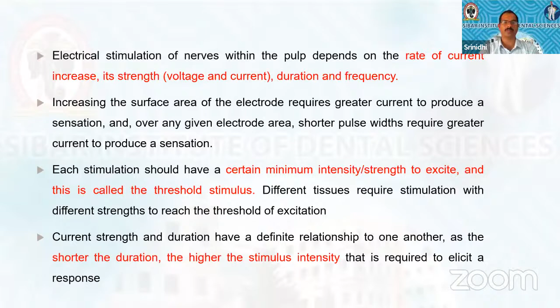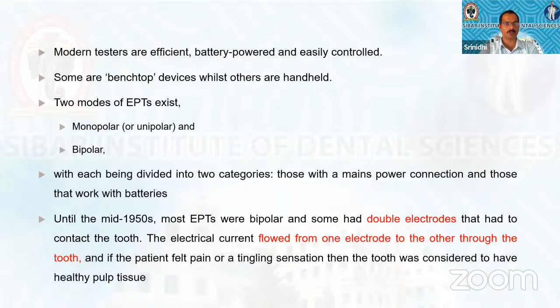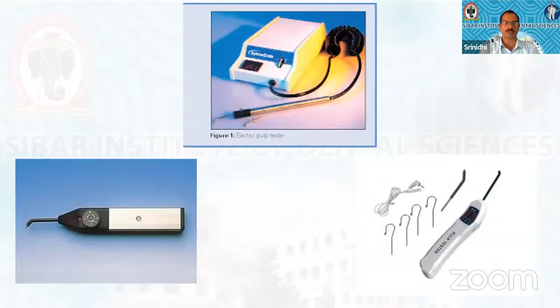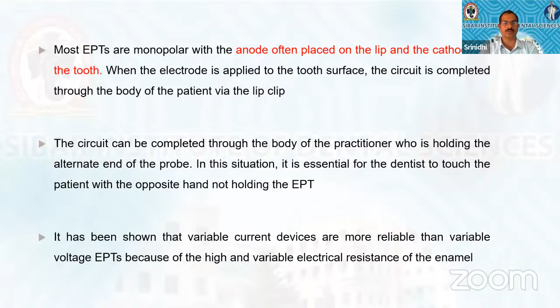So we have two types of EPT, monopolar and bipolar. What we commonly use is the monopolar, where we have a single electrode. In bipolar, we have two electrodes which are placed on the tooth, and the current passes from one electrode to the other. We also have benchtop or handheld devices, and most EPTs are monopolar, with the anode often being the lip clip and the cathode being the probe that is kept on the tooth. And the circuit is always completed either by the use of the lip clip, or by the body of the practitioner, or by the patient holding the end of the probe.